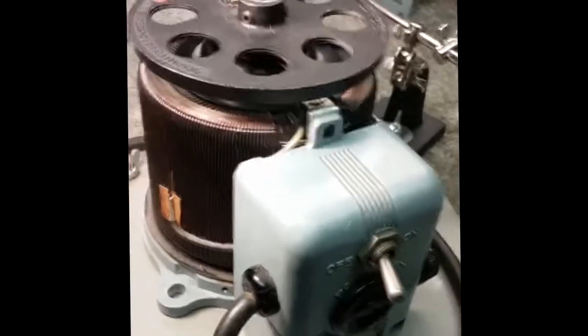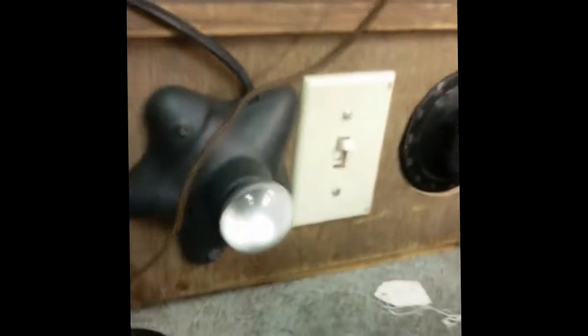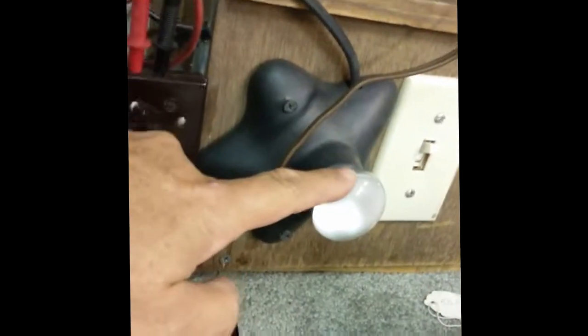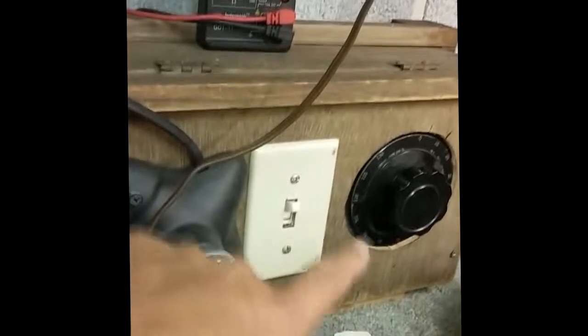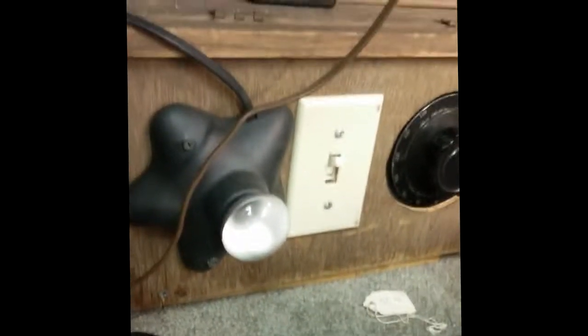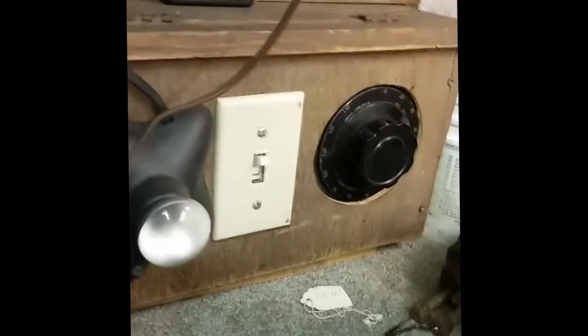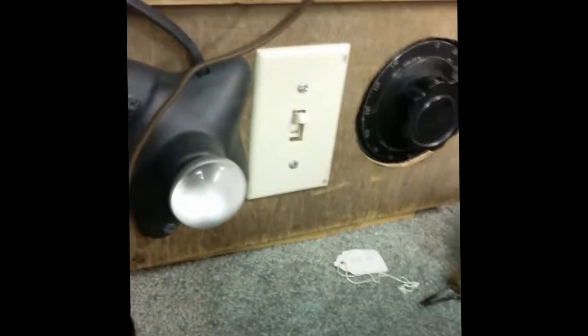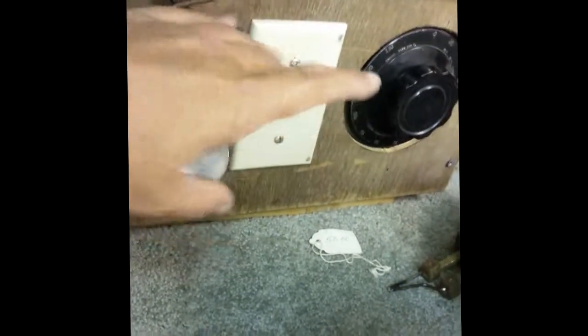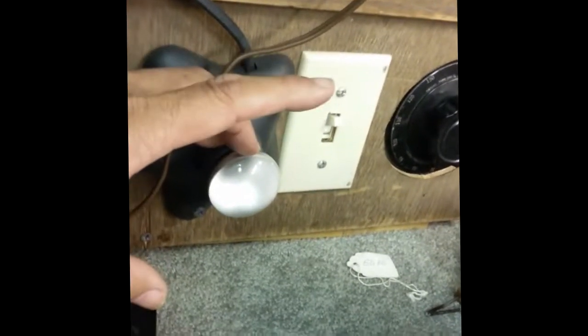This is a newer model than the one I'm using. I'm using an old rheostat here, which is connected in this box, and I got it connected with a light backup, but I also have in the box an isolation transformer. So I am backed up by a current limiting light bulb. I also keep one of my outlets connected to a voltmeter, so as I adjust the voltage, I know what voltage I'm using on my output. But by having an isolation box like this with an isolation transformer and a rheostat, you protect yourself and your equipment, which you don't want to blow up, from your circuit as you're working. And to test for shorts, I can turn this on, and the bulb will light. And if the bulb lights real bright, then I know there's a short in the circuit.